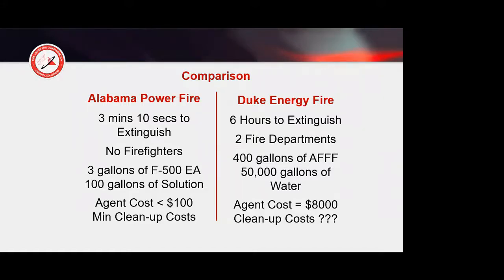They called the local emergency responders as soon as the alarms went off that they had a transformer fire. The F500 put the fire out, and they turned the emergency responders around before they ever arrived at the first gate. So they used a total of 100 gallons of solution and only 3 gallons of F500. They had a minimum cleanup cost.